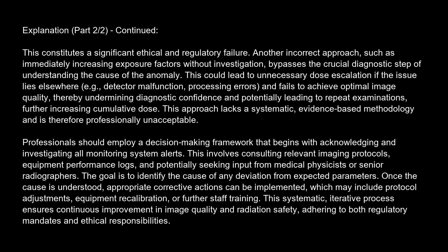Another incorrect approach, such as immediately increasing exposure factors without investigation, bypasses the crucial diagnostic step of understanding the cause of the anomaly. This could lead to unnecessary dose escalation if the issue lies elsewhere, e.g., detector malfunction, processing errors, and fails to achieve optimal image quality, thereby undermining diagnostic confidence and potentially leading to repeat examinations, further increasing cumulative dose.